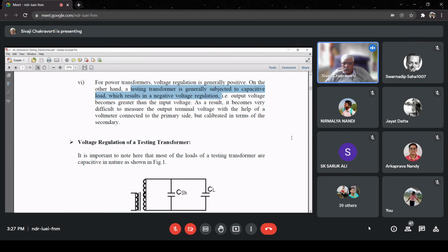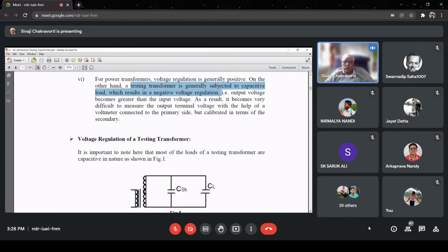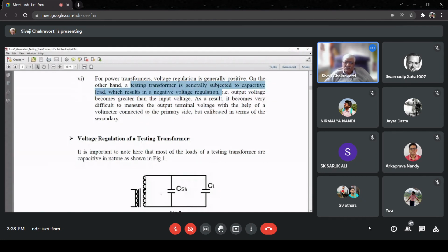Now, why is it so? I tell you one thing why it is so important. Now you can see this equivalent circuit. Normally, what we do, we put a voltmeter to measure how much voltage I am applying. So I am putting a voltmeter across the transformer terminal. But now there is an interesting thing that this voltage, if I measure it under open circuit condition, and then I apply this voltage to this load, the voltage that will appear across the equipment will be higher than the voltage which we have measured at the transformer terminal open circuit condition.